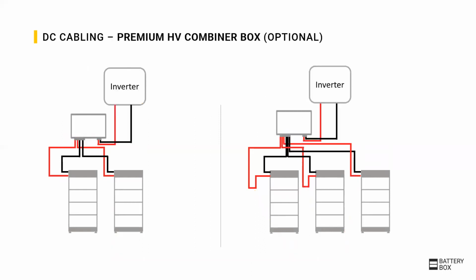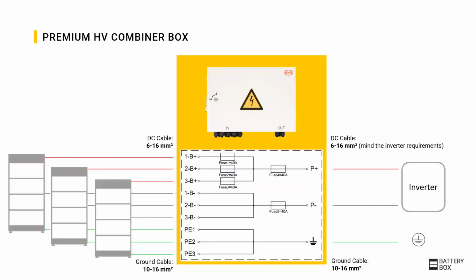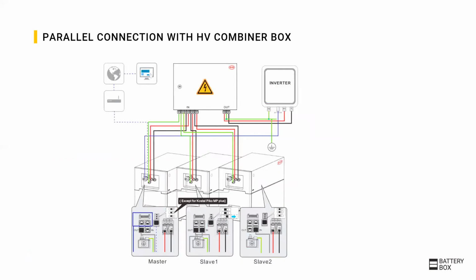BYD also offers an optional in-house solution to simplify the DC cabling with a premium HV combiner box. Here, basically all DC cables and the ground cables of the different towers are collected. Internal fuses protecting the cabling enable smaller cable cross-sections that might be necessary for the inverter. Here, the complete cabling for a parallel system with 3 towers and the HV combiner box is shown.